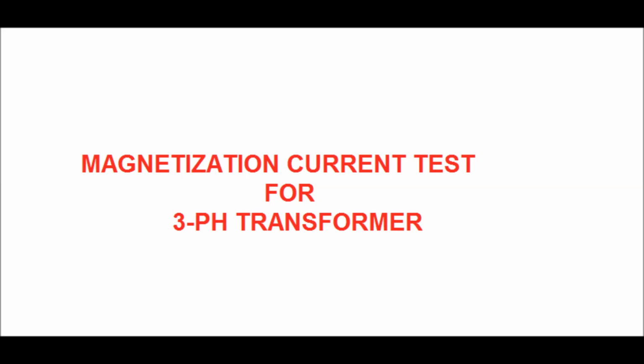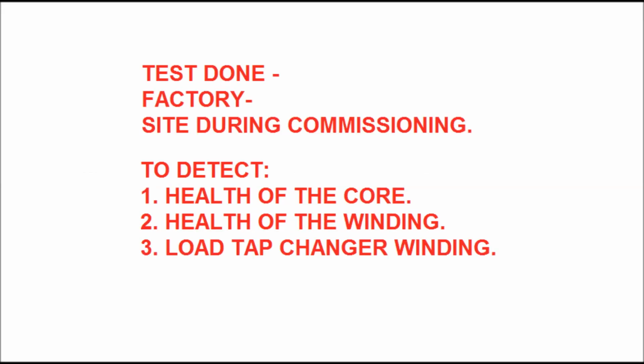Hello friends, today I will discuss the magnetization current test for a three-phase power transformer. This test is done at the factory end and also during commissioning of the transformer. This is done mainly to detect, number 1, the health of the core, number 2, the health of the winding, that is the primary winding as well as the secondary winding, number 3, the health of the on-load tap changer winding.